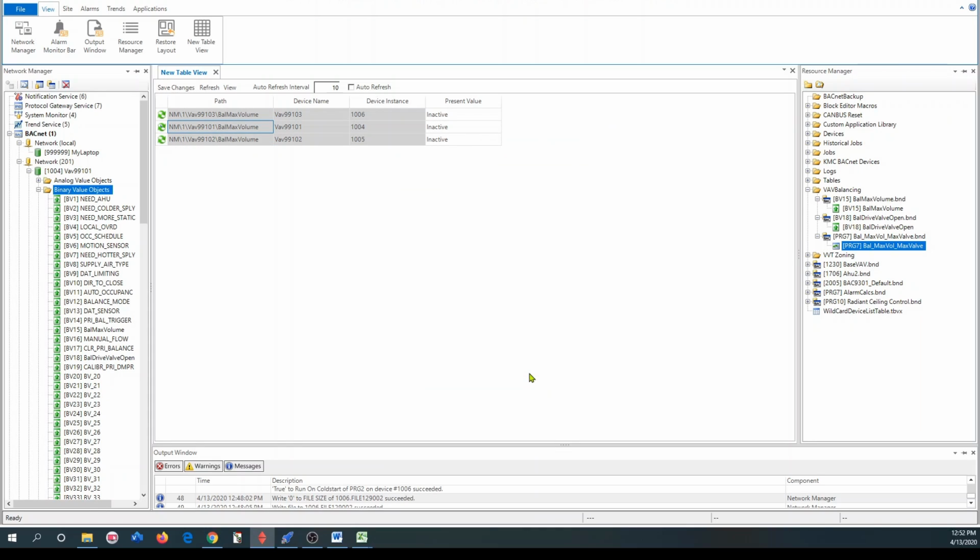Okay, now I know it got into all three of those controllers because it came up here. Now, if for some reason it didn't go into one of the controllers, you would see BV15 or whatever name that object used to be instead of this name right here. So that's the reason for using just the mnemonic and not the address. Okay, so let's try another one here.